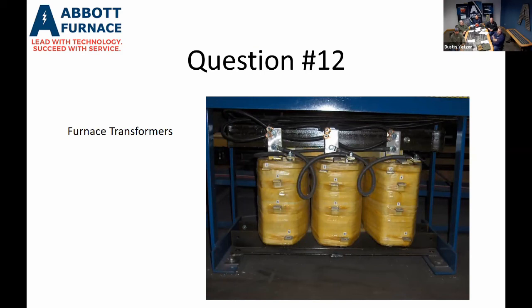So if you had a 60 kVA transformer, the max amps that you're allowed out to that transformer is going to be 72 amps. Okay. So if you move up a tap and you would happen to hit that 72 amps, the SCR is going to start cutting the voltage back and trying to protect from overheating that transformer. A lot of customers don't realize that when they put all new glow bars in their zone and they were on tap 4, and you're putting too high of a voltage on there and your SCR is cutting it way back, you actually lose power by doing that.